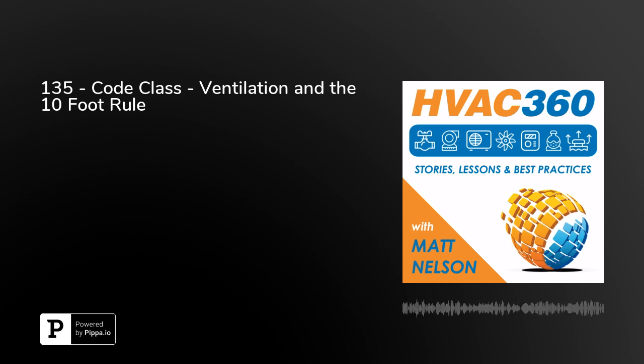Number two: it has to be at least 10 feet horizontally from hazardous or noxious sources. This means other vents, alleyways, loading docks, things like that. They go through a specific list. It's important to know exactly what you're looking at, because if it doesn't fall into that category, you can use engineering judgment to say it's not listed, but here's the intent, and this is how I'm interpreting the code. So you can have your engineering opinion on this. If it's less than 10 feet horizontally from one of these noxious, hazardous sources, it has to be 25 feet above those. That's the stipulation for number 2.